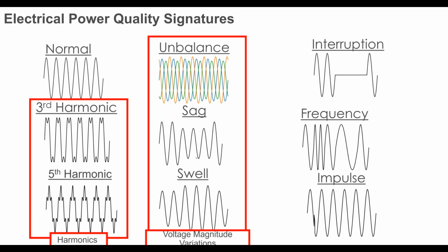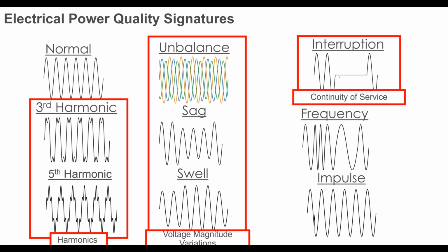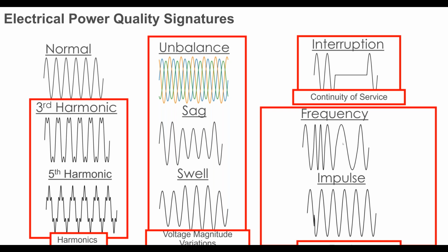Looking at another power quality signature, when you have unbalanced load, you have different phases in a three-phase system, with different magnitudes for each of the phases. A voltage sag occurs when the load that is consuming power is beyond what the generation can handle. A voltage swell is when the generation is much more than the load that's consuming power. All of this basically introduces inefficient use of energy. And then we have interruption, where a breaker opens, and the consumer sees just no power. This is the power quality signature signifying a lack of continuity in service. And then there's the frequency. This frequency has to be regulated within a certain tolerance, but here's the signature of where you see a frequency excursion.